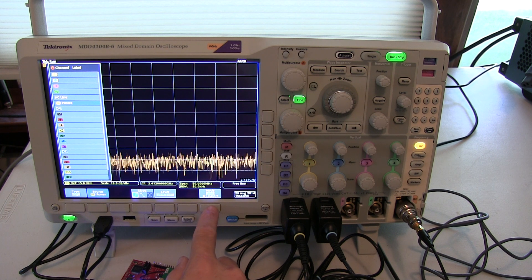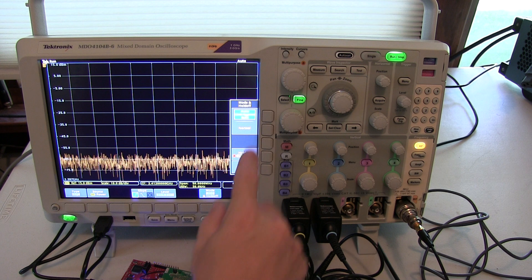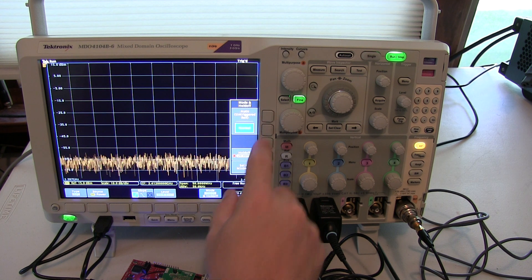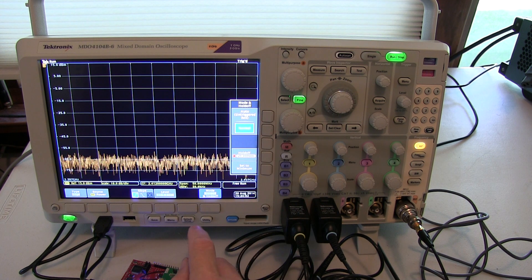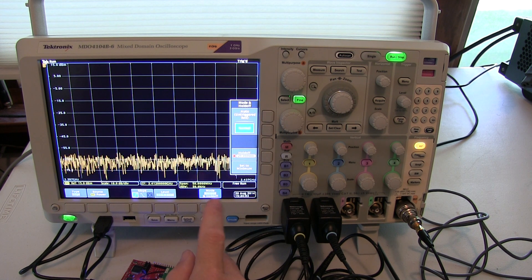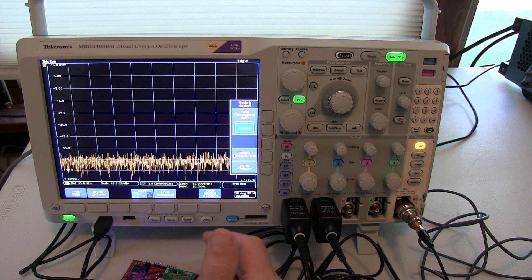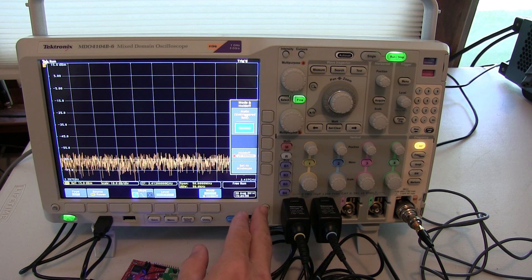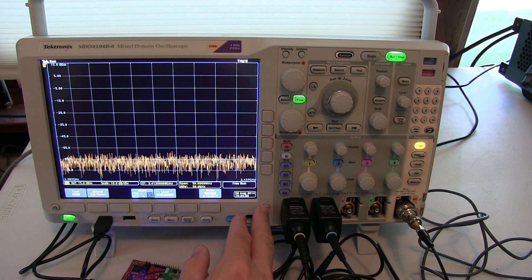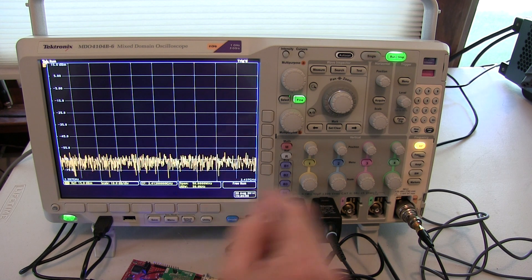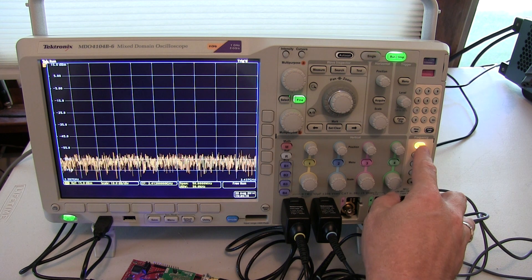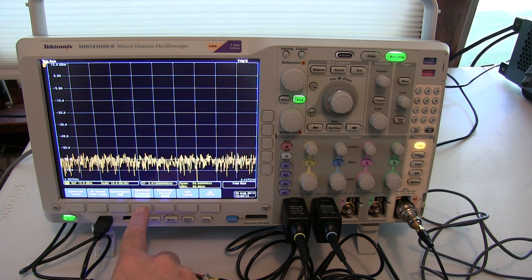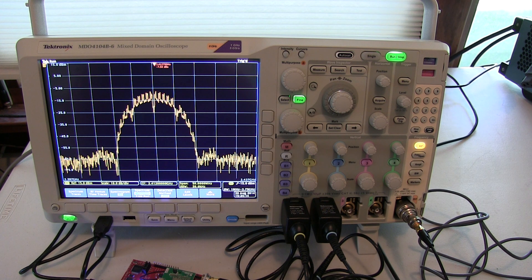I'm going to change the trigger mode from auto to normal, and that will ensure that we're only going to trigger during that one-second burst and not in between. So the next thing we need to do is just tell the spectrum analyzer to be triggered instead of free running.